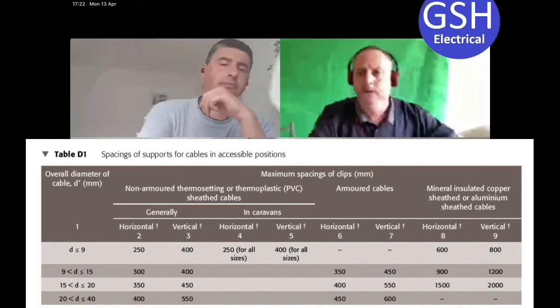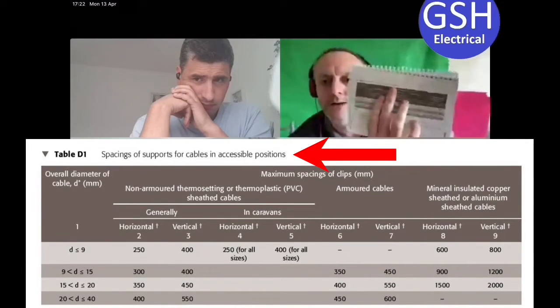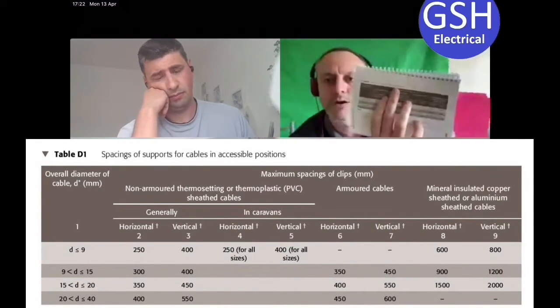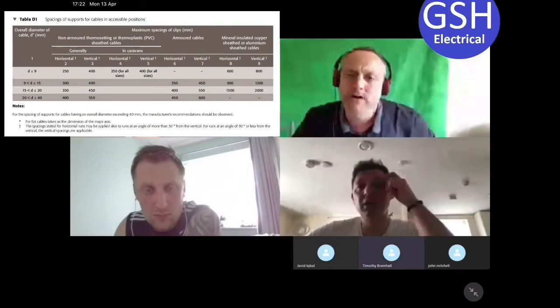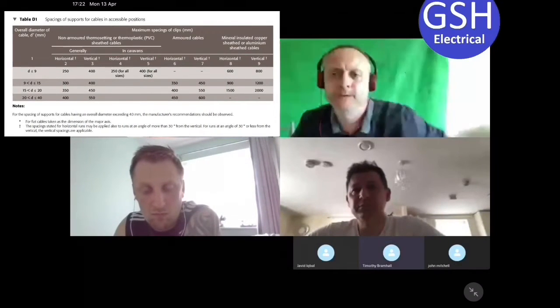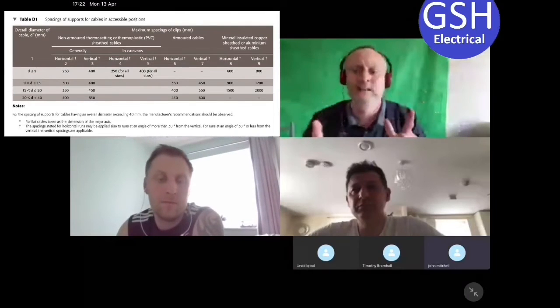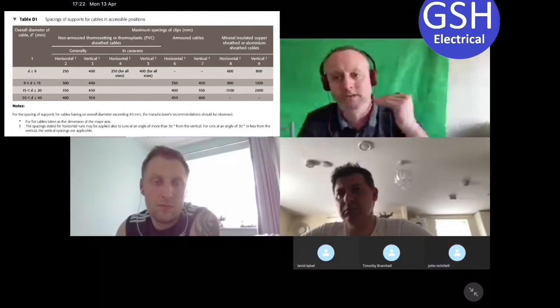Look at the title - it says 'in accessible positions'. So for cables clipped to a joist that's then plasterboarded with a floor over it, those cables are not accessible. In that instance, there isn't necessarily a need to abide absolutely by this rule. But when I was clipping cables, I clipped to support the cable properly and applied the distances accordingly anyway.